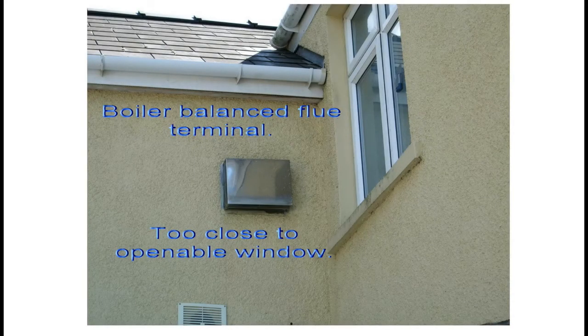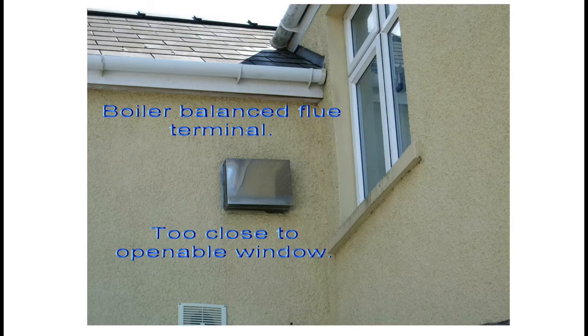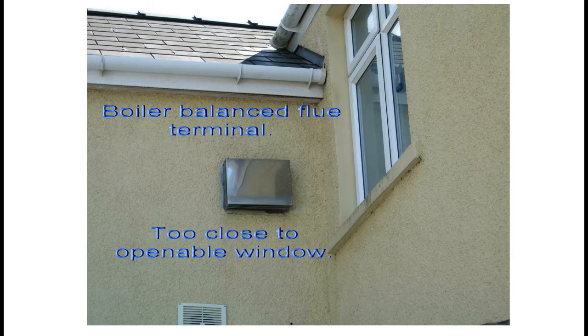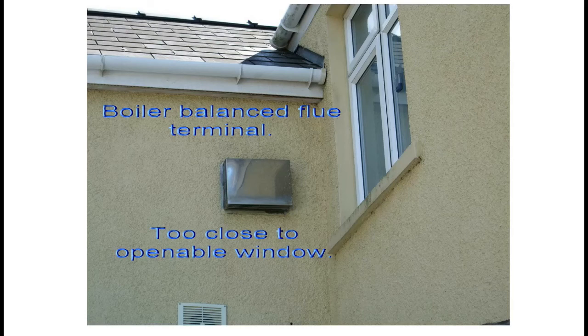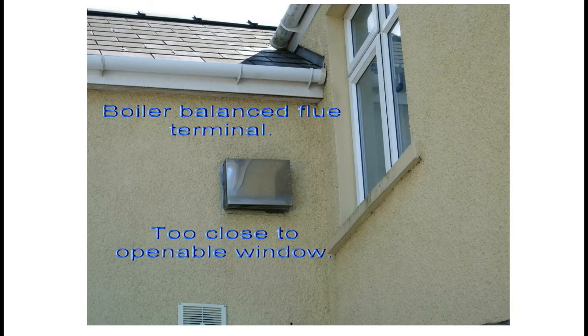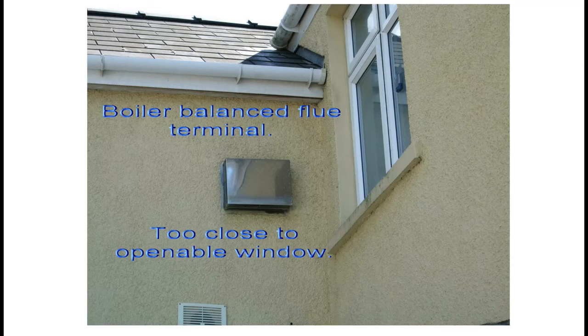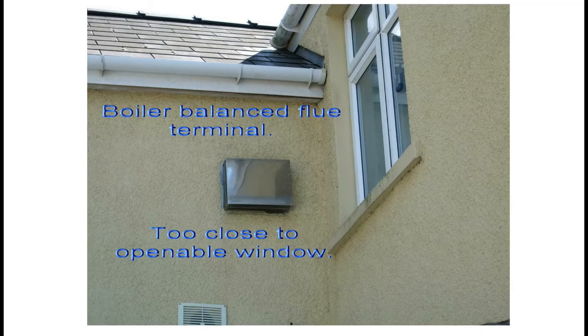Here's a real life example of a balanced flue terminal, which is too close to an openable window. So this is a natural draft balanced flue. You can tell that because it's made of metal. And it's a big square shiny terminal in general. These are natural draft terminals.